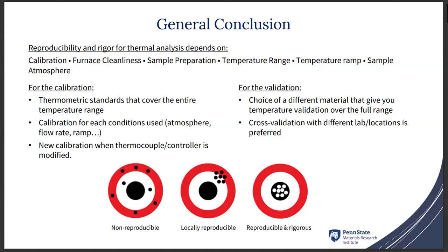So for the calibration, we need to use a thermometric standard that covers the entire temperature range. One point is not enough. The calibration needs to be done for each condition that is used, so atmosphere, flow rate, and ramp, and the calibration needs to be redone every time there is a change of thermocouple or the controller is modified, because this affects the temperature you will get. For the validation, this is extremely important. You need to choose a material that gives you a temperature validation over the range, so something that changes over time, which is what the magnesium stabilized aluminum titanate was used for. And if you can, use a cross-validation with different labs at different locations to make sure that you get the same results.